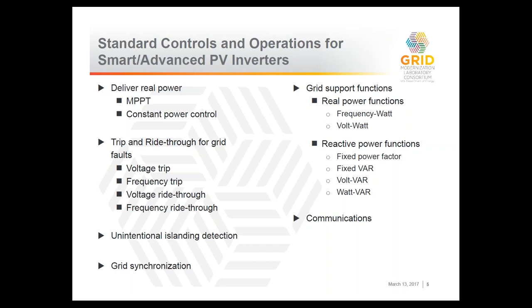And then there is also unintentional islanding detection, where you are detecting a grid fault and tripping, meaning if there is a big grid fault, where there is no power on the distribution circuit, then your inverter needs to detect it and trip as soon as possible, typically within 2 seconds. There are grid synchronization requirements. Obviously, when you are connecting back to the grid, you need to synchronize to the grid. And then there are some grid support functions that are being implemented nowadays in the inverter.